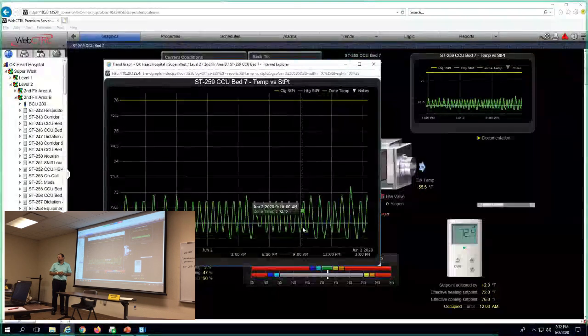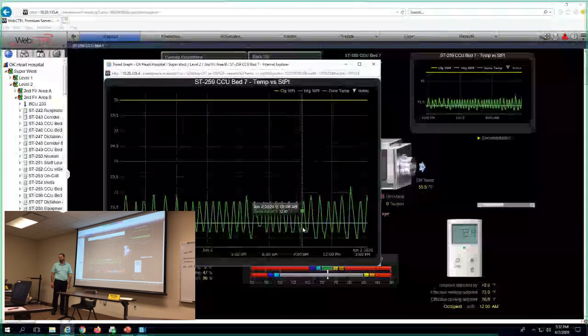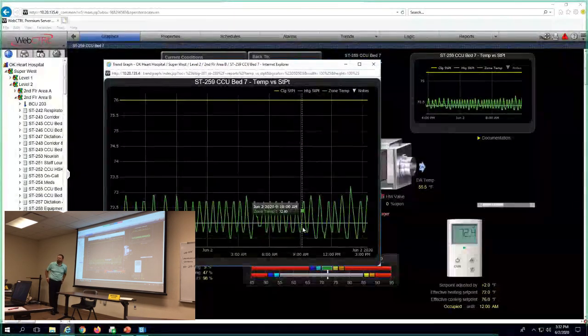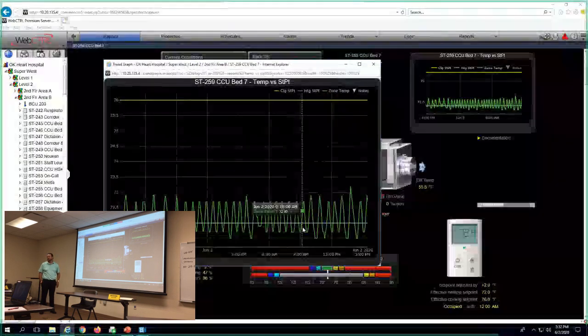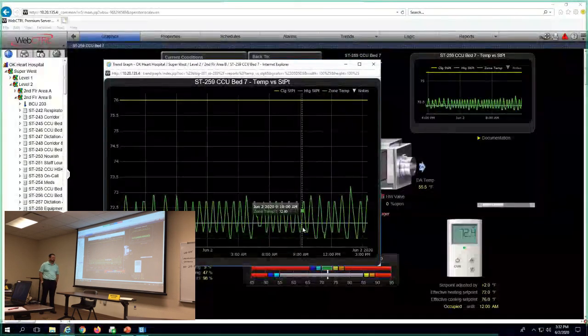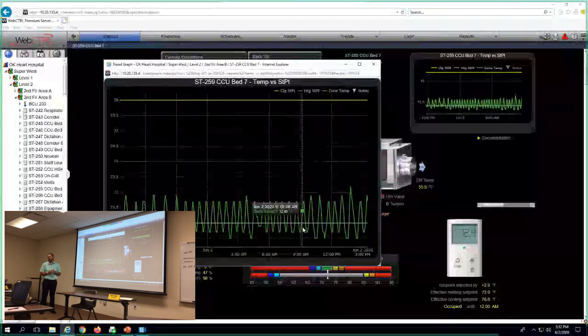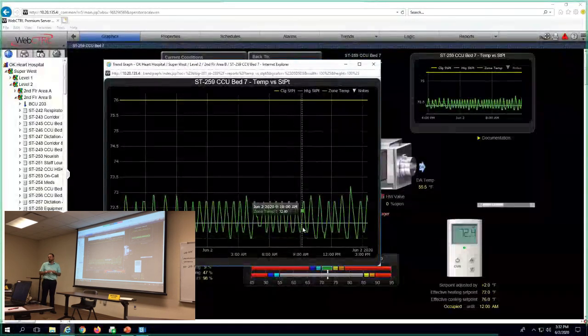What you don't want is an adjustment of 4 degrees and a deadband of 4 degrees, because the nurse is going to say, I'm cold, I'm going to bump this up, but it's going to take the setting up to 76, and it's not going to do anything. It's still satisfied. They're still going to hang out at 72 and it's still going to be cool because it's still satisfied. That's what I was thinking. That's why I think the deadband needs to be 2 degrees. It'd be closer to what you guys probably have on your Johnsons.